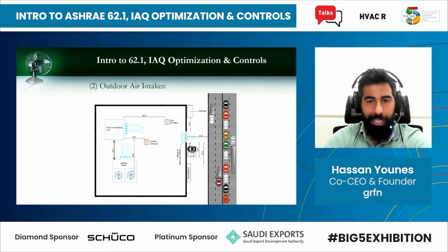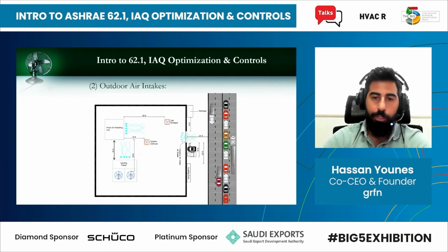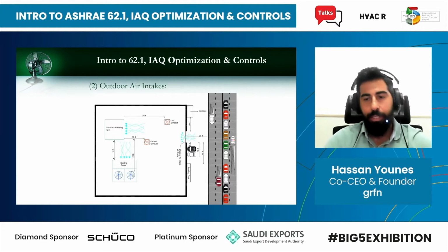so that they basically have good indoor air quality. Outdoor air intakes: it's basically the separation distance that's required between the air intakes and any pollutant sources. These pollutant sources could be exhaust from the building. As you can see in this illustration that I drew with one of the drafting team members in maybe 2010, I believe, there are different pollutant sources. The road could be one, garbage, cooling towers, exhaust, kitchen exhaust, lab exhaust. And there's a minimum distance that you need to separate the outdoor air intakes from those so that no contamination can be recirculated back to your building. Or if you have any other sources of contamination like the road or garbage cans, then you need to have a minimum distance between the intake and those pollutant sources.